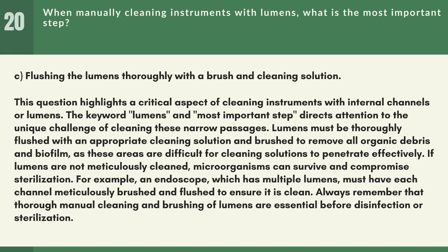Answer: C. Flushing the lumens thoroughly with a brush and cleaning solution. This question highlights a critical aspect of cleaning instruments with internal channels or lumens. The keyword lumens and most important step directs attention to the unique challenge of cleaning these narrow passages. Lumens must be thoroughly flushed with an appropriate cleaning solution and brushed to remove all organic debris and biofilm, as these areas are difficult for cleaning solutions to penetrate effectively.